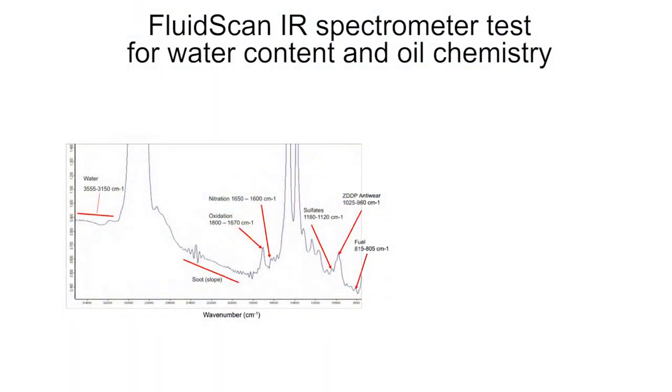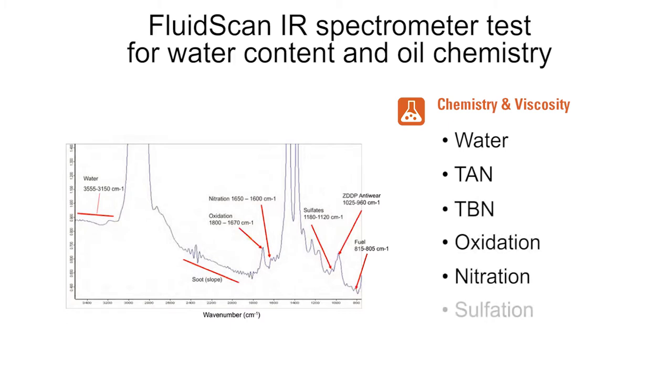All tests for water content and oil chemistry are done on the FluidScan infrared spectrometer. It measures water, total acid, total base, oxidation, nitration, sulfation, and other oil-specific properties.